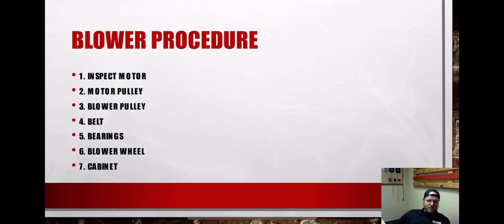And then your blower procedure, same thing. You've got to perform your blower procedure. When I say perform your blower procedure, you've got to inspect the motor. Turn the unit off. What does it look like, right? If you're doing your blower procedure, the unit is off 100%. Double check that disconnect. Double check your electrical. But inspect the motor. Get in there. Get on top of it. Feel it with your hands. Is it hot? Is it cold? Has it been running? Does it smell?